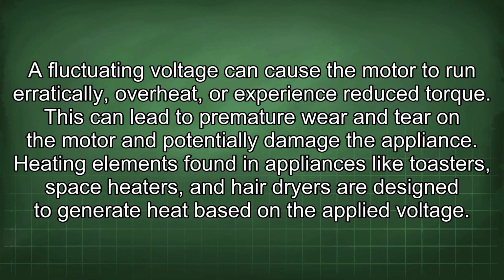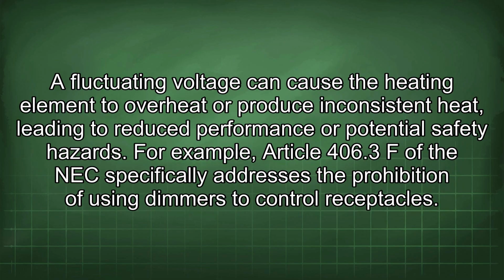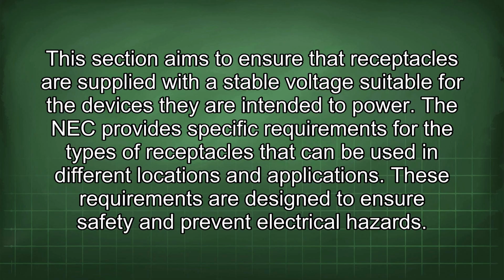Heating elements found in appliances like toasters, space heaters, and hair dryers are designed to generate heat based on the applied voltage. A fluctuating voltage can cause the heating element to overheat or produce inconsistent heat, leading to reduced performance or potential safety hazards. For example, Article 406.3(F) of the NEC specifically addresses the prohibition of using dimmers to control receptacles. This section aims to ensure that receptacles are supplied with a stable voltage suitable for the devices they are intended to power. The NEC provides specific requirements for the types of receptacles that can be used in different locations and applications. These requirements are designed to ensure safety and prevent electrical hazards.